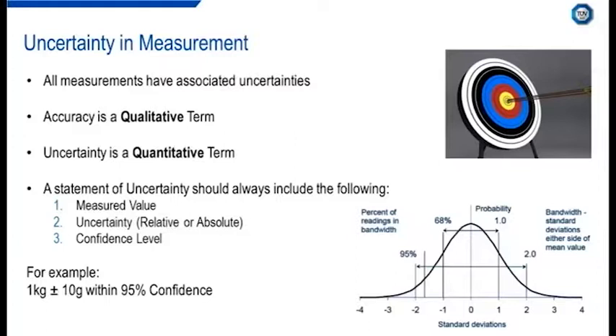For example, if we have measured a mass to be 1 kilogram plus or minus 10 grams within a 95% confidence level, what we're saying is that we are 95% confident that the true value lies between 990 grams and 1,010 grams. 1 out of every 20 readings will lie outside the uncertainty margins for a 95% confidence level. The wider the uncertainty limits, the more confident we can be that the true value lies within the limits.